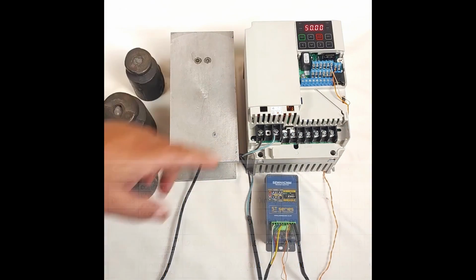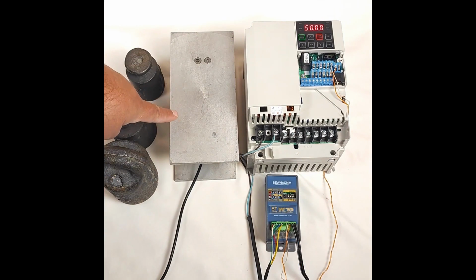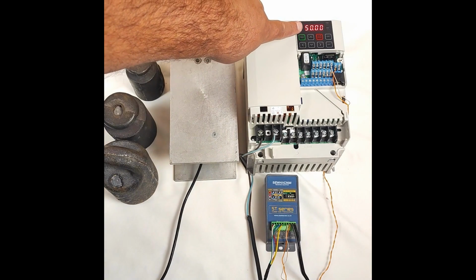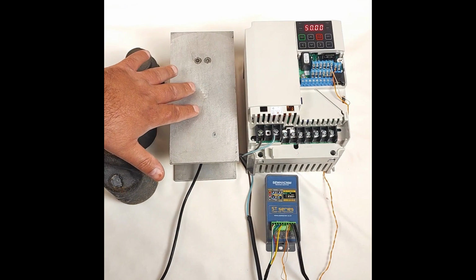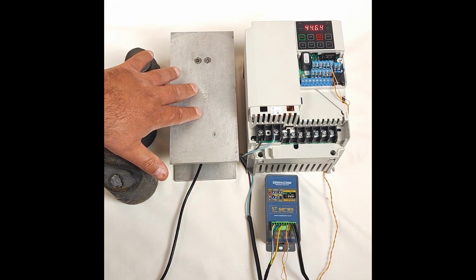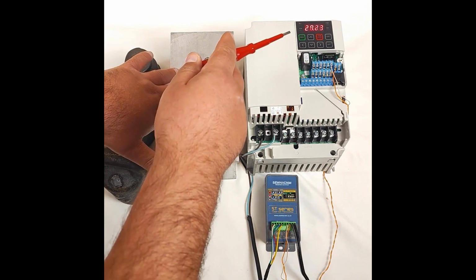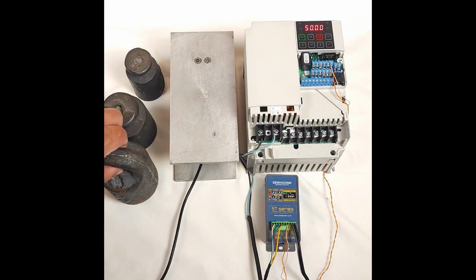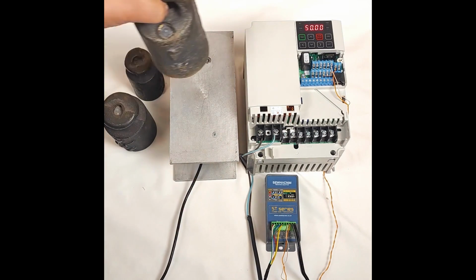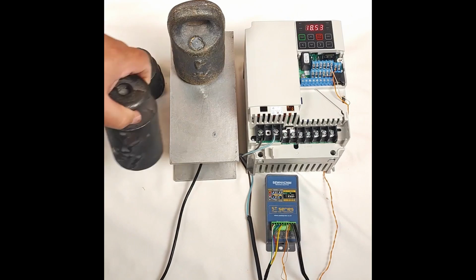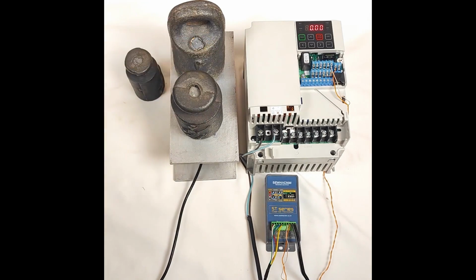As you can see, the load cell is currently unloaded. The transmitter is showing 4 milliamps and the drive frequency is 50 Hz. If I apply some force to the load cell, you can see the frequency changes. Now, if I place the full load, which is 5 kilograms, on the load cell, we see that the drive frequency has dropped to 0.